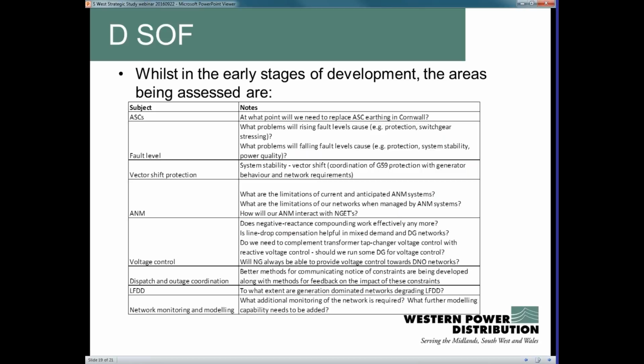Fault levels: changes in the nature of generation, in terms of type and the mix between what's on distribution networks versus transmission networks, will impact fault levels. That impacts power quality, in terms of dips and harmonics on the network, but could also affect our protection systems. So we need to understand how that will change in the future.